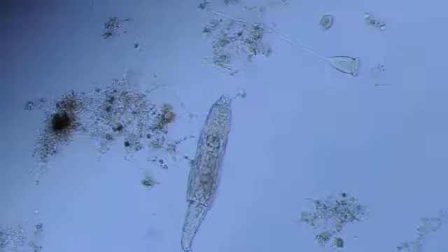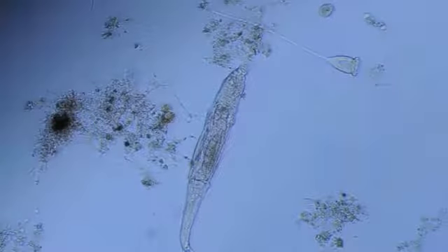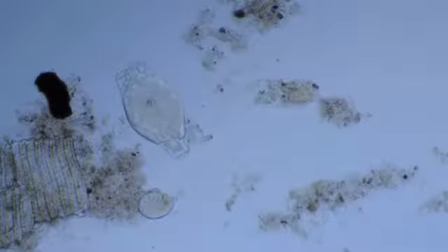And rotifers. These are a higher life form with cool hairy mouths and are much larger than many of the other bugs we see here. Some forms are much more mobile and move around constantly. Others, a little bit less active. And our worm friends, the nematodes. These tiny worms, who can be active or just swimming lazily around the neighborhood, can also be an indicator of some certain conditions. Both nematodes and rotifers can be indicative of an older bacterial biomass and in wastewater are indicative of a higher degree of purification or seeding from an attached growth system.